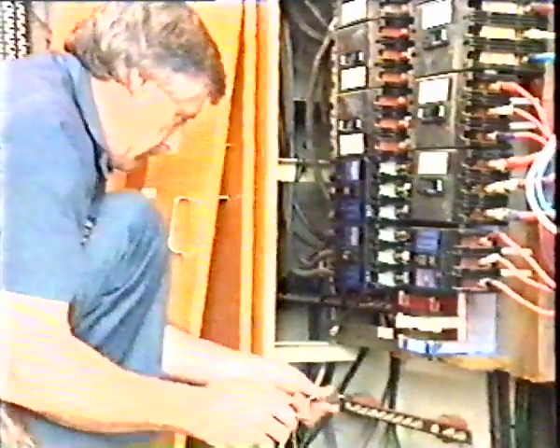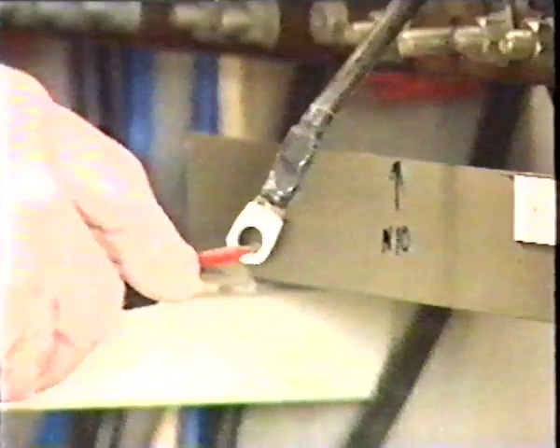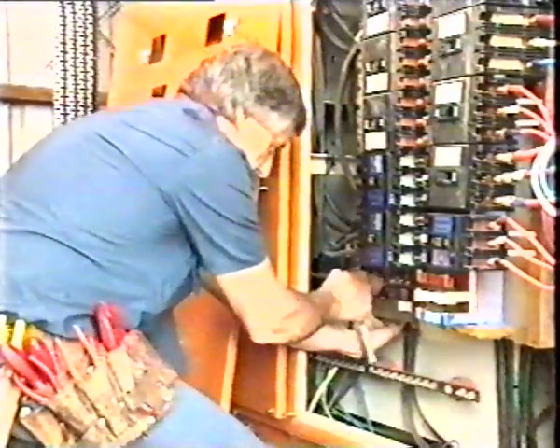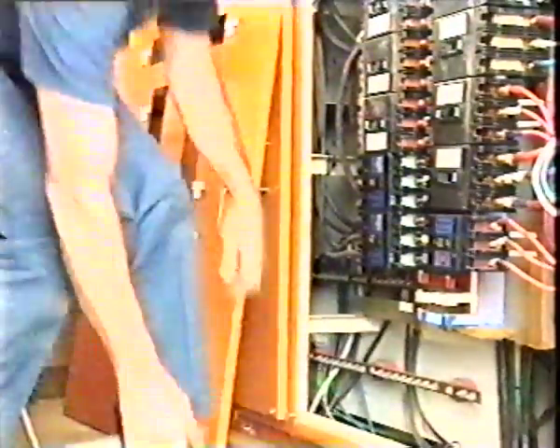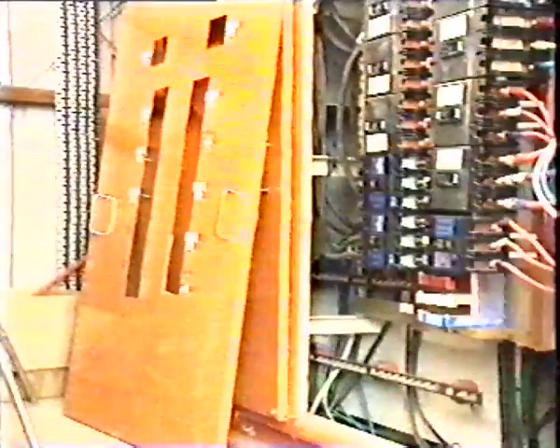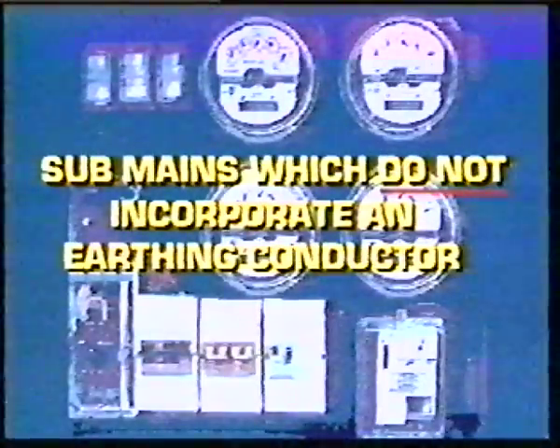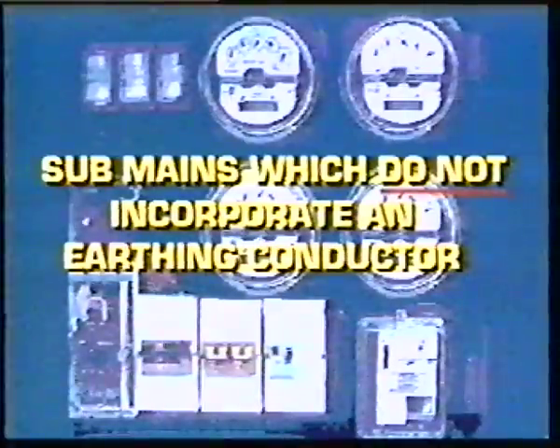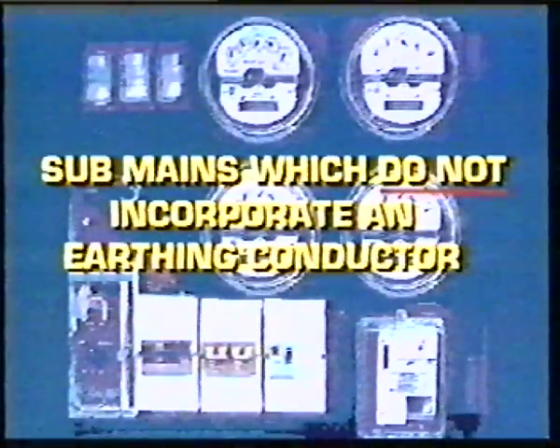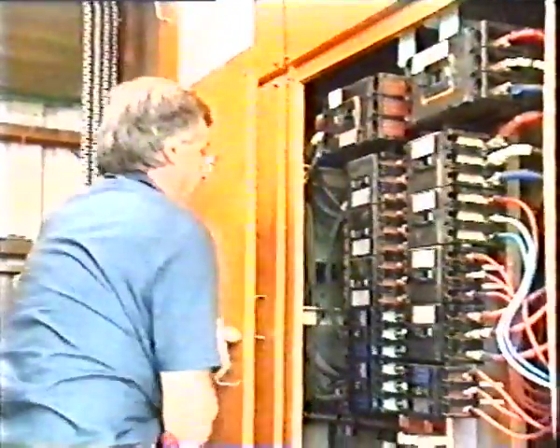Disconnect the submain neutral conductor from the supply switchboard neutral link. Test the insulation resistance of the conductor. Reconnect the submain neutral conductor to the neutral links at the supply switchboard and distribution board. Now for submains which do not incorporate an earthing conductor. Disconnect supply at the origin of the submains, again by opening the protective devices at the supply switchboard.